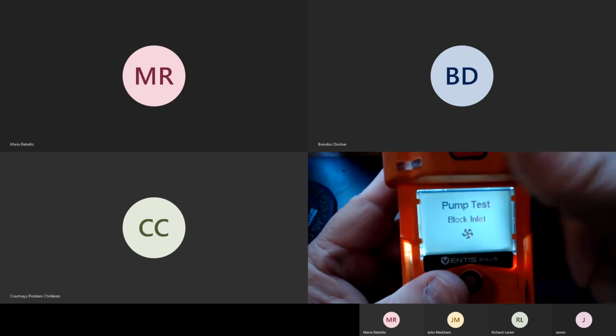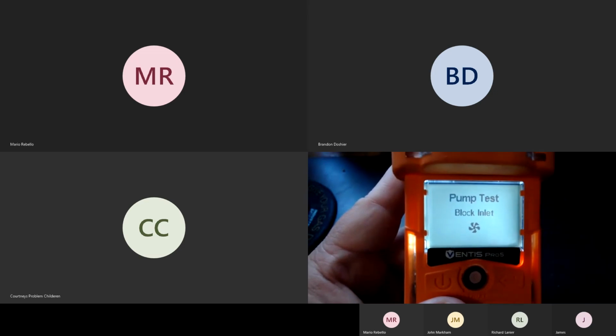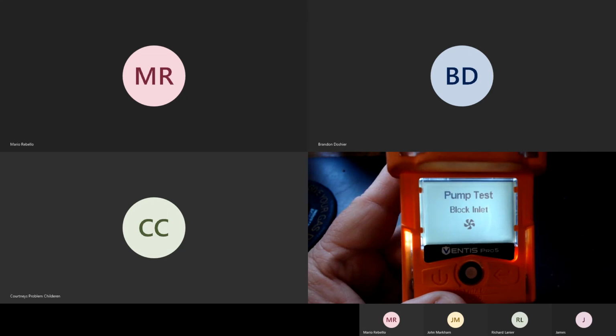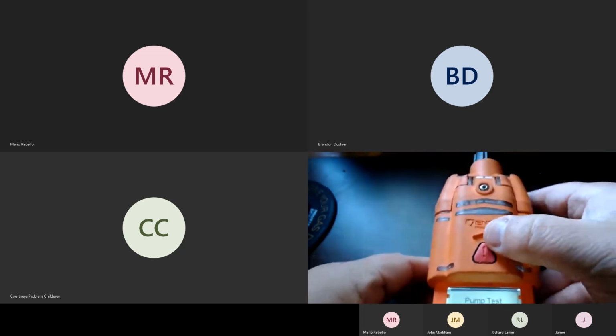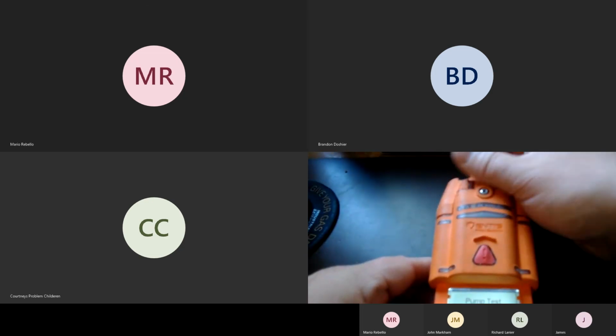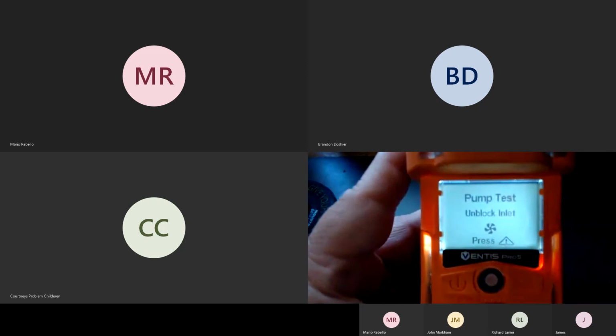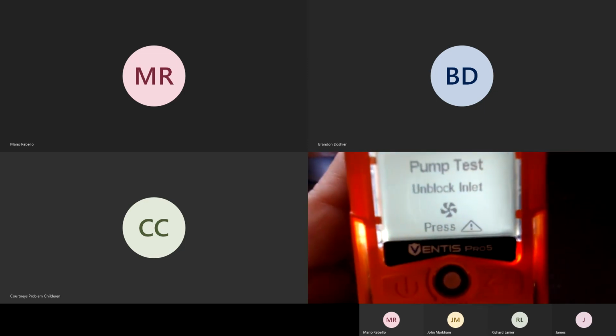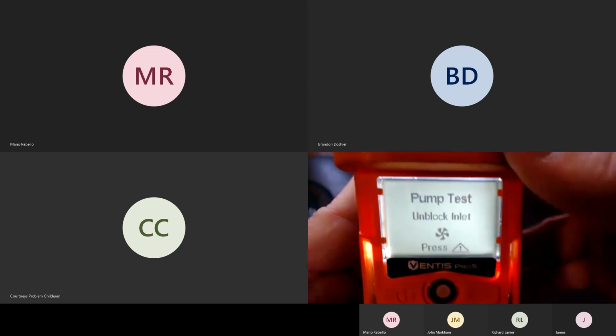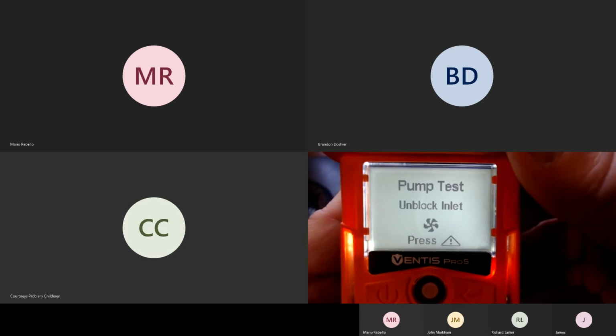And then what you have to do is a pump test. This is different. This is not a bump test. This is the pump test. To do the pump test, just take your finger and stick it over the pump inlet. It will kind of stall out the pump. The pump may stop completely. It may not. It all depends on the flow of the pump.